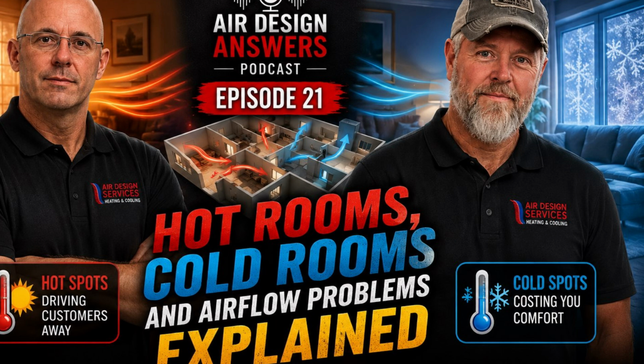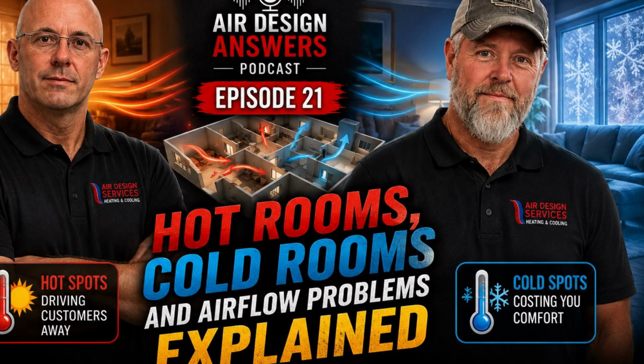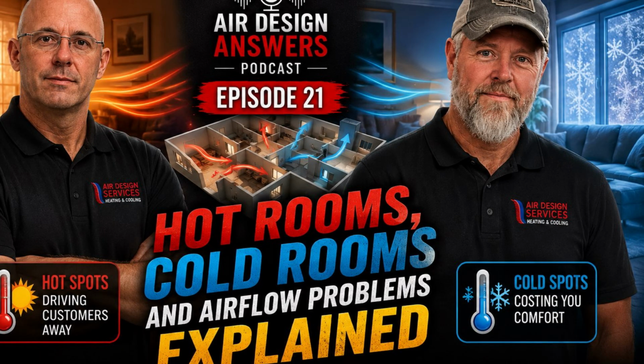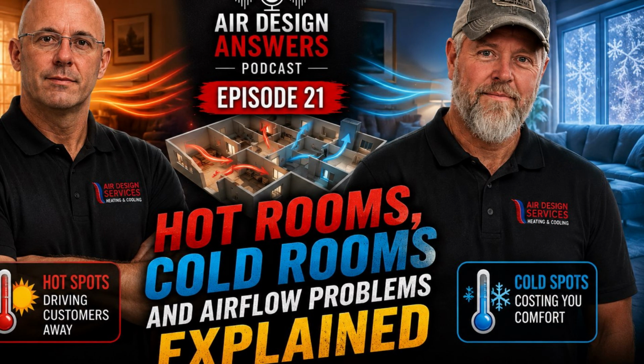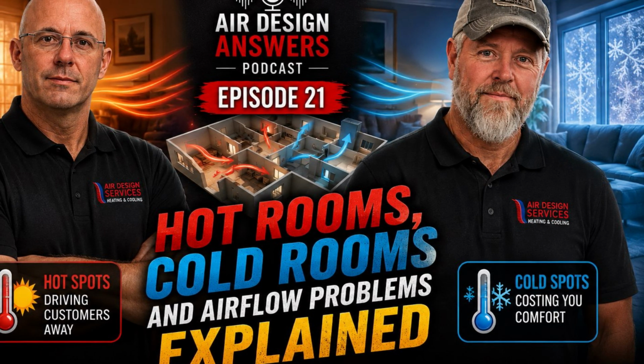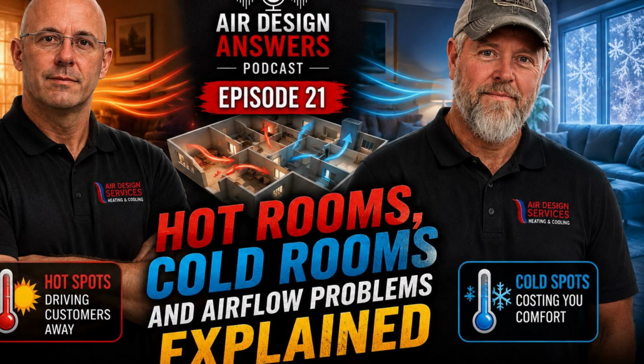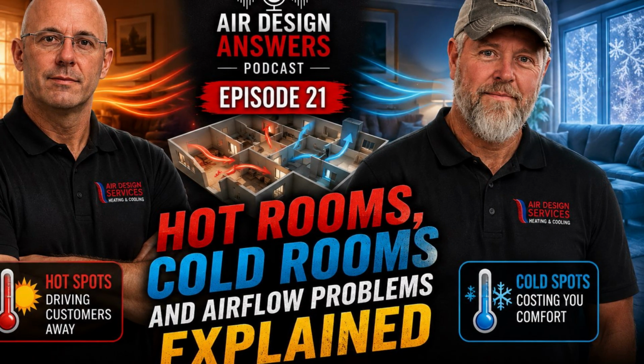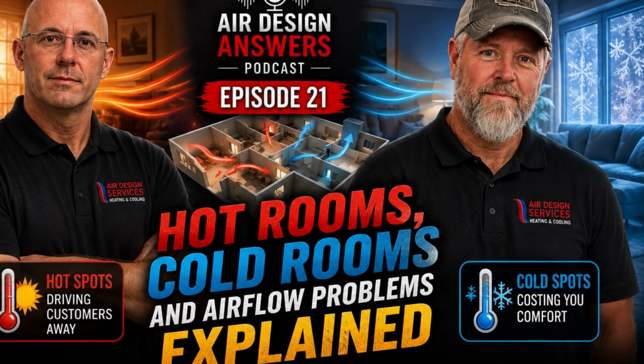The next thing I'd suggest is checking the simple stuff first. Make sure vents are open. Make sure returns aren't blocked. Make sure furniture isn't restricting airflow. Check the furnace filter. Those are easy things homeowners can evaluate themselves. And sometimes the solution really is that simple. We've had service calls where a blocked return grill was causing comfort complaints throughout an entire section of the home.